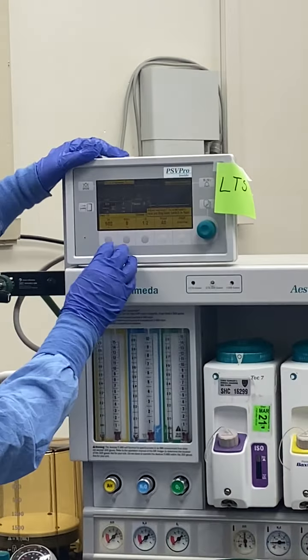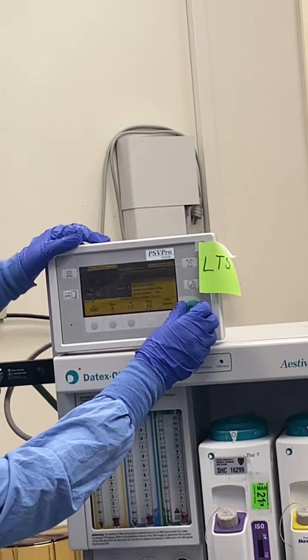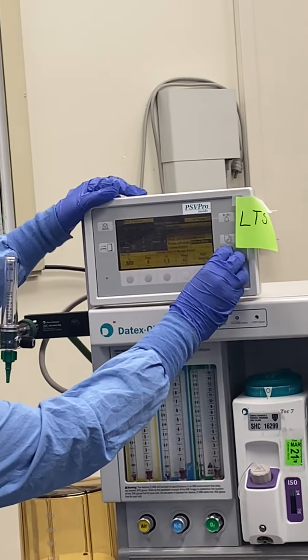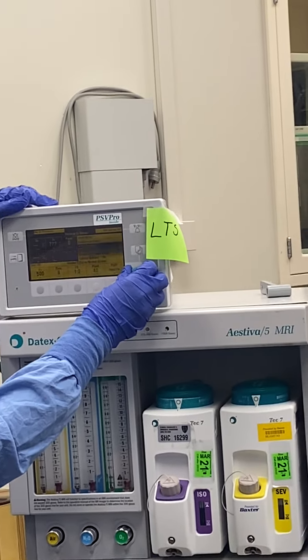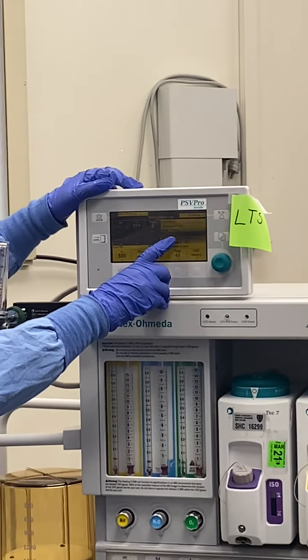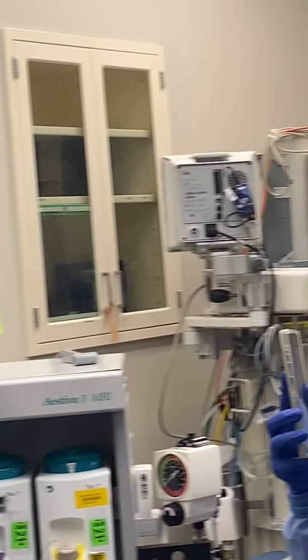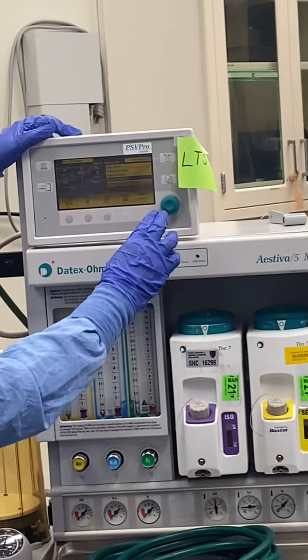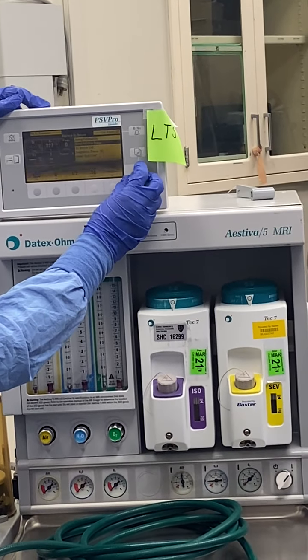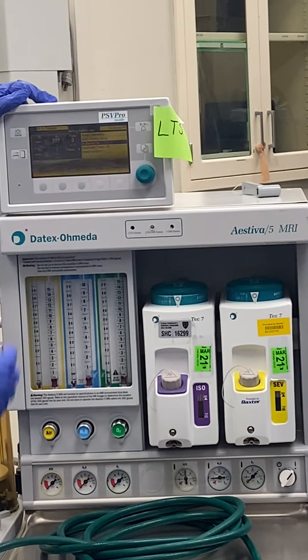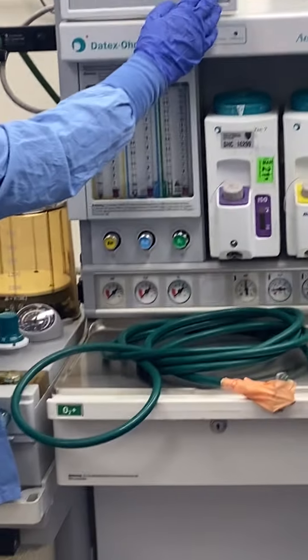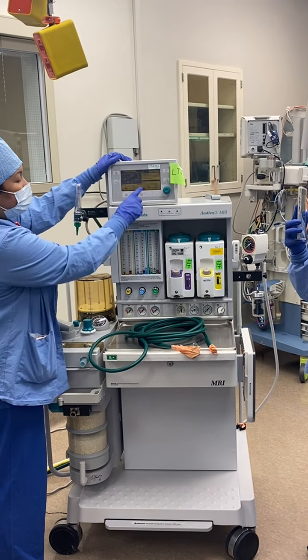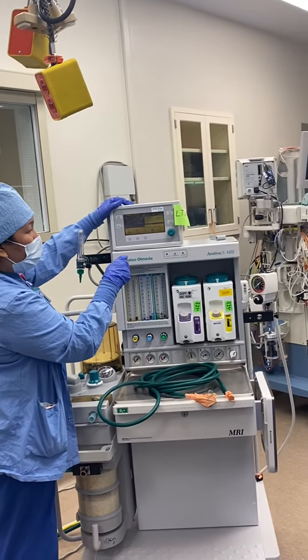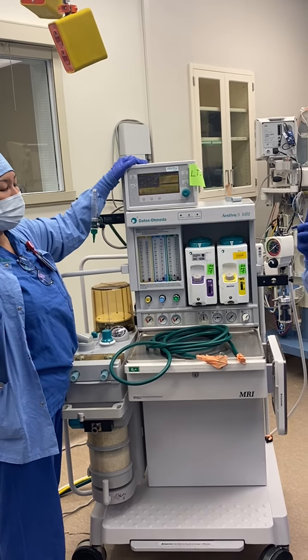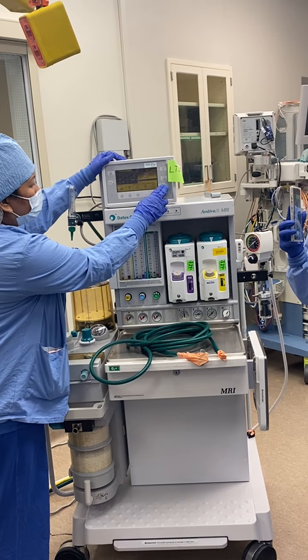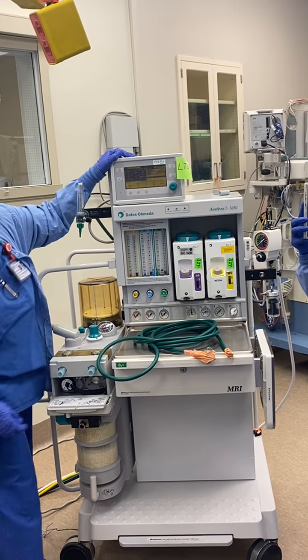So, I'm going to go set up this machine. I'm going to go under setup. Okay? I'm going to press setup. And in order to confirm, you have to push the knob. And then I need to calibrate the O2 sensor. The O2 sensor is down here. I press OK. And it says, complete 21% first. 100% calibration may be performed only after 21% calibration has been completed. So I'm going to go to 21%. I'm going to open my sensor here.